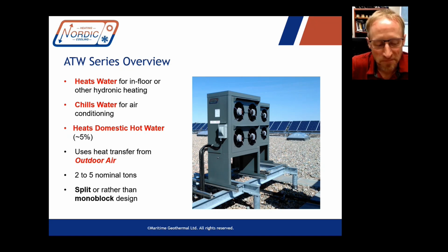Okay. The hot water. So one potential strategy for passives, they're very inertial, as you can imagine, right? They don't change quickly with the outside temperature, the indoor temperature. So one strategy is actually to run a system at a lower capacity, but especially if you have a buffer tank, you're going to have a steadier draw. You're not going to have as peaky of a draw from that tank. Yeah. So I'm wondering if you actually had a smaller capacity heat pump that's running more regularly, maybe continuously throughout the day for a bunch of the winter, you could get more hot water capacity, domestic hot water output out of that strategy. Could you?